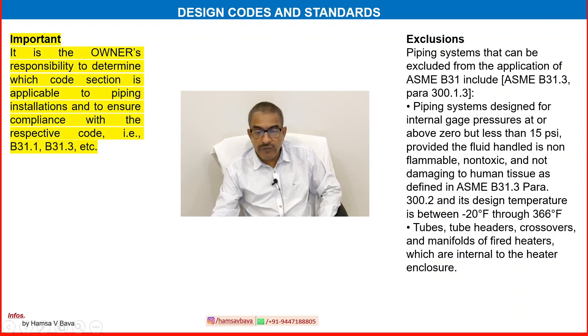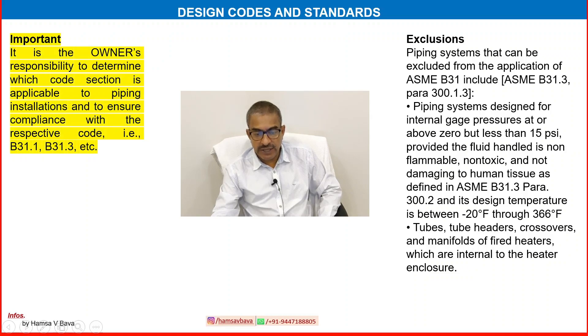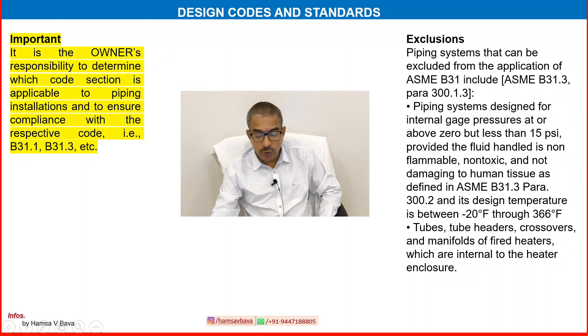Some exclusions from the application of ASME B31 are included — see ASME B31.3 para 300.1.3. Piping systems designed for internal gauge pressures at or above 0 but less than 15 PSI may be excluded, provided the fluid handled is non-flammable, non-toxic, and not damaging to human tissue as defined in ASME B31.3 para 300.2, and its design temperature is between -20°F and 366°F. Also excluded are tubes, tube headers, crossovers and manifolds of fired heaters which are internal to the heater enclosure.